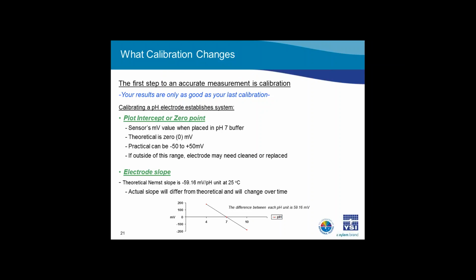Let's first address calibration. The absolute best thing you can do to obtain accurate, repeatable measurements is to ensure you are performing a good calibration on your pH system. The system includes the meter and the electrodes.